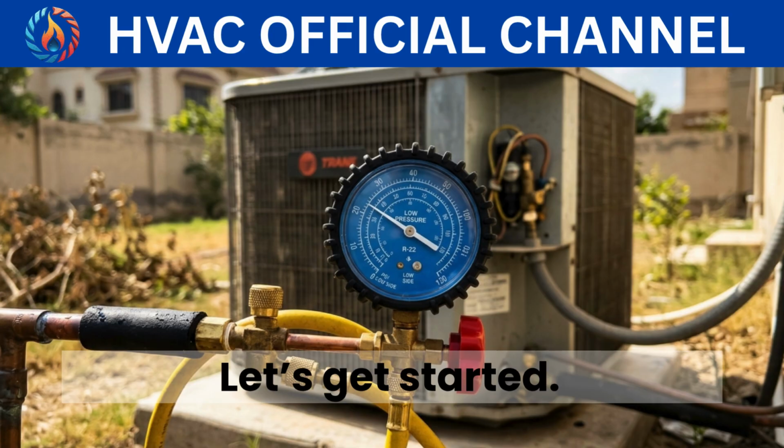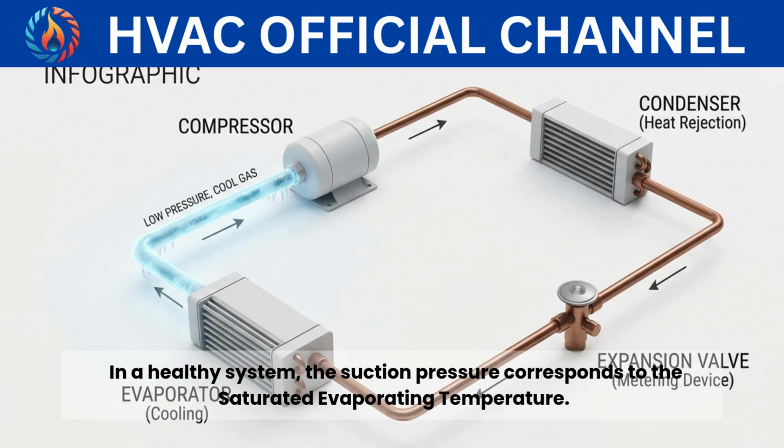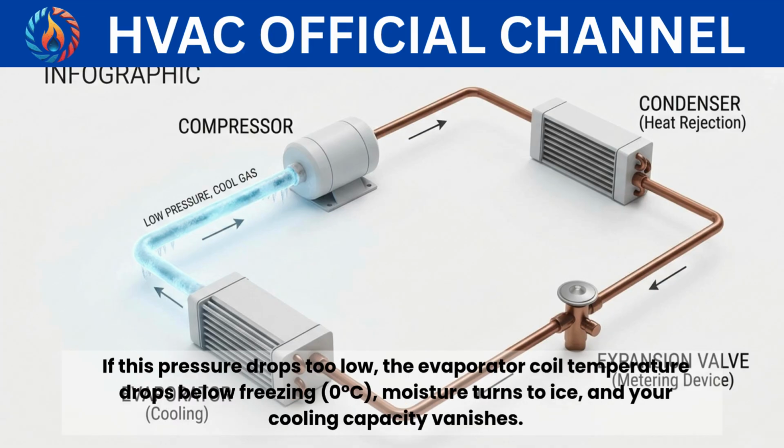Let's get started. What is suction pressure? Before we fix it, we must define it. Suction pressure is the pressure of the refrigerant as it enters the compressor from the evaporator. In a healthy system, the suction pressure corresponds to the saturated evaporating temperature. This temperature must be lower than the room air so that heat can move from your room into the refrigerant. If this pressure drops too low, the evaporator coil temperature drops below freezing, 0 degrees Celsius, moisture turns to ice, and your cooling capacity vanishes.